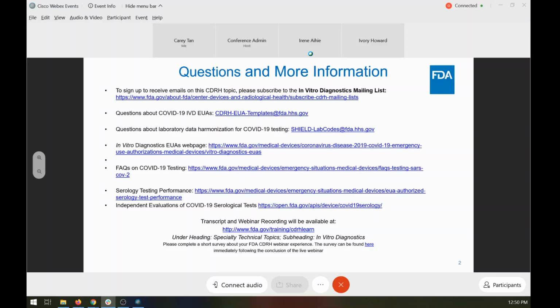Yeah, so it would be great to understand which elements are necessary to go in, and if this could then carry forward for 510K as well. So perhaps I will send you a question in the EUA templates email, and maybe that could be answered that way. Does that make sense? Sure, and I think the device labeling regs, especially the IVD specific labeling regs, are a good place to start. So we would want to make sure that all of those labeling requirements are covered.